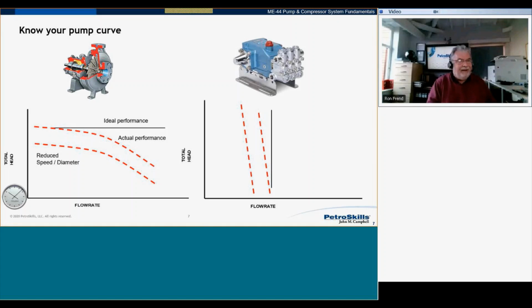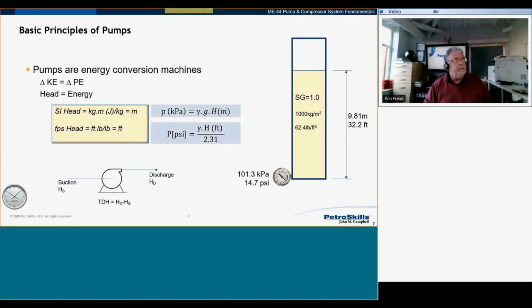I'm going to concentrate mainly on the centrifugal pumps. And I want to explore first of all, what's this thing about head? Because a lot of people get confused about the difference between head and pressure. Okay, head. When we say head, what we're talking about is energy. And if we look at these units, if I've got head there, in SI units, we use meters. Where that comes from, really I should be using kilonewton meters there, but we could use kilogram meters. Kilogram meters of energy that we put into the liquid for every kilogram of mass of that liquid. So we cancel out the kilograms and we end up with meters.